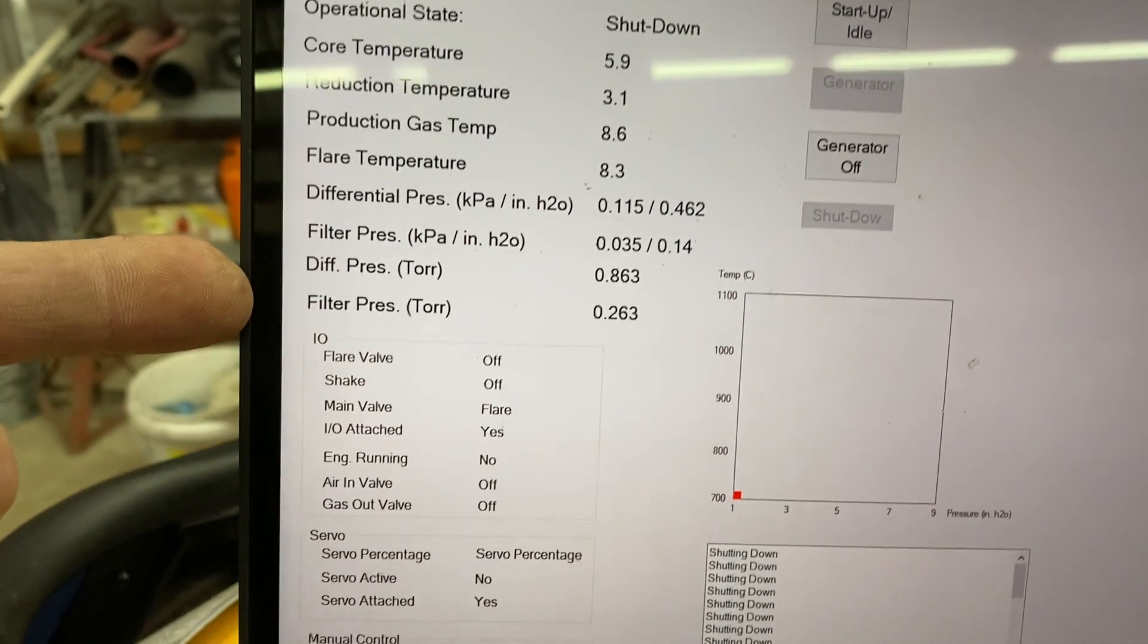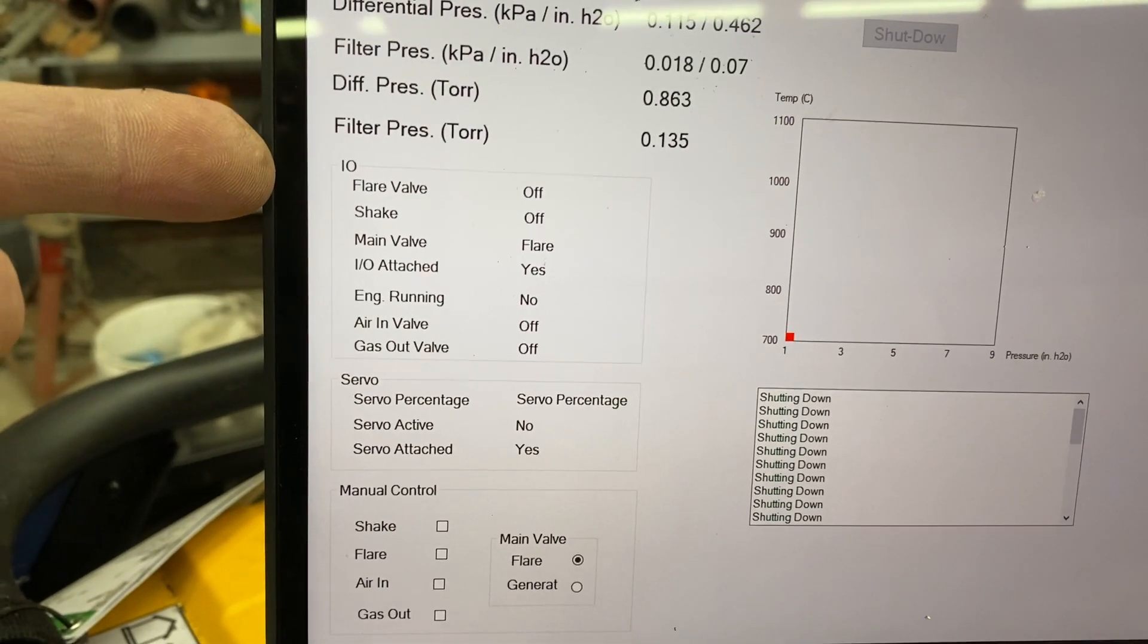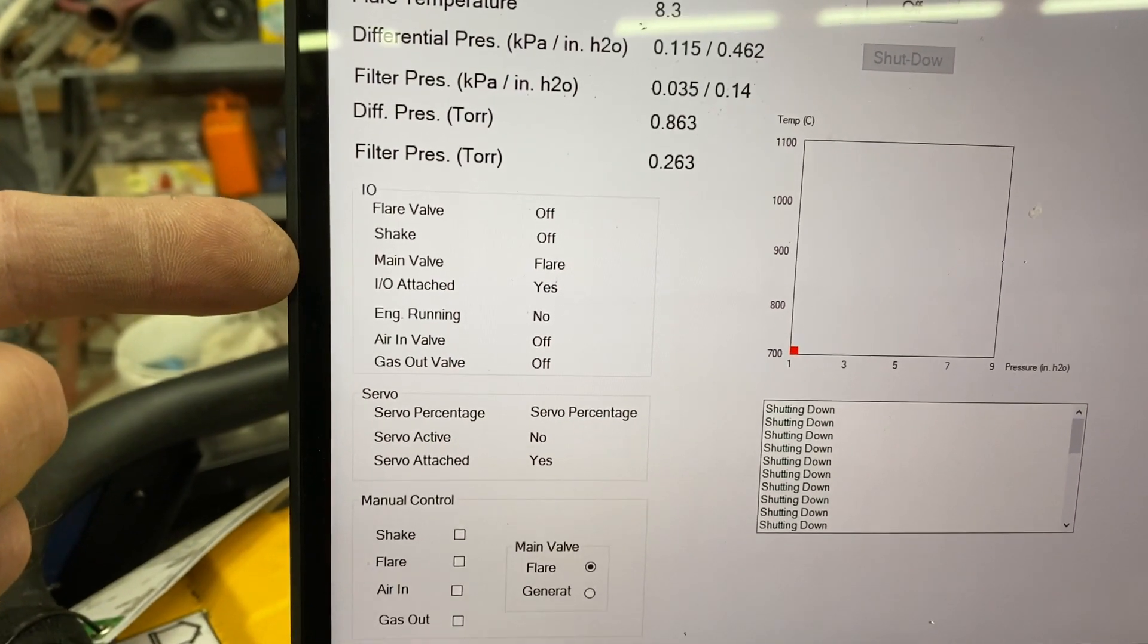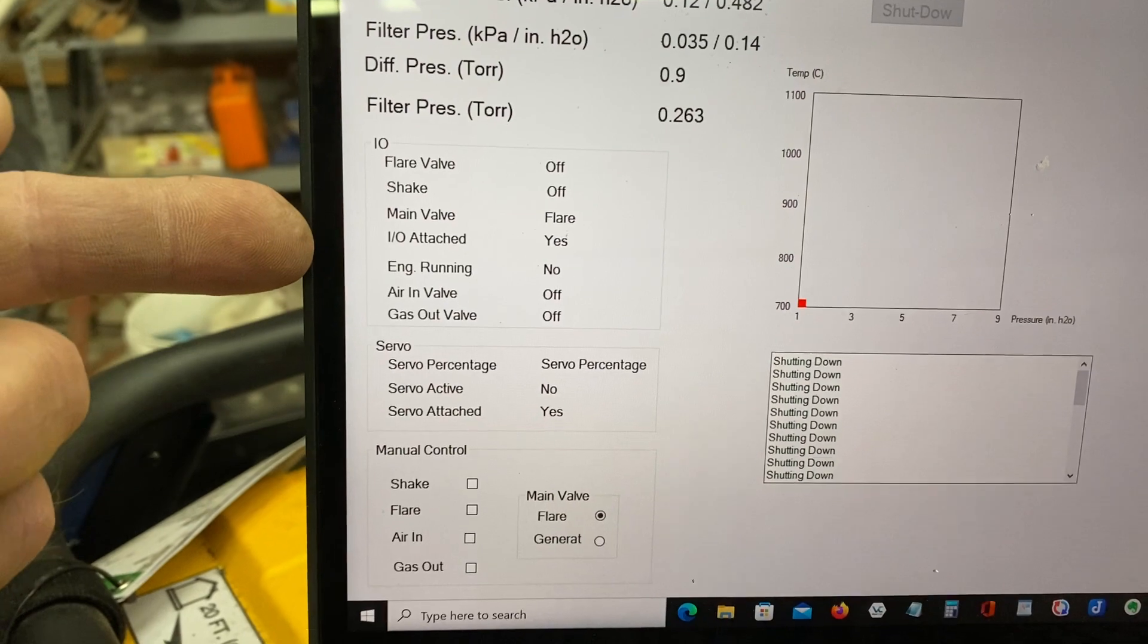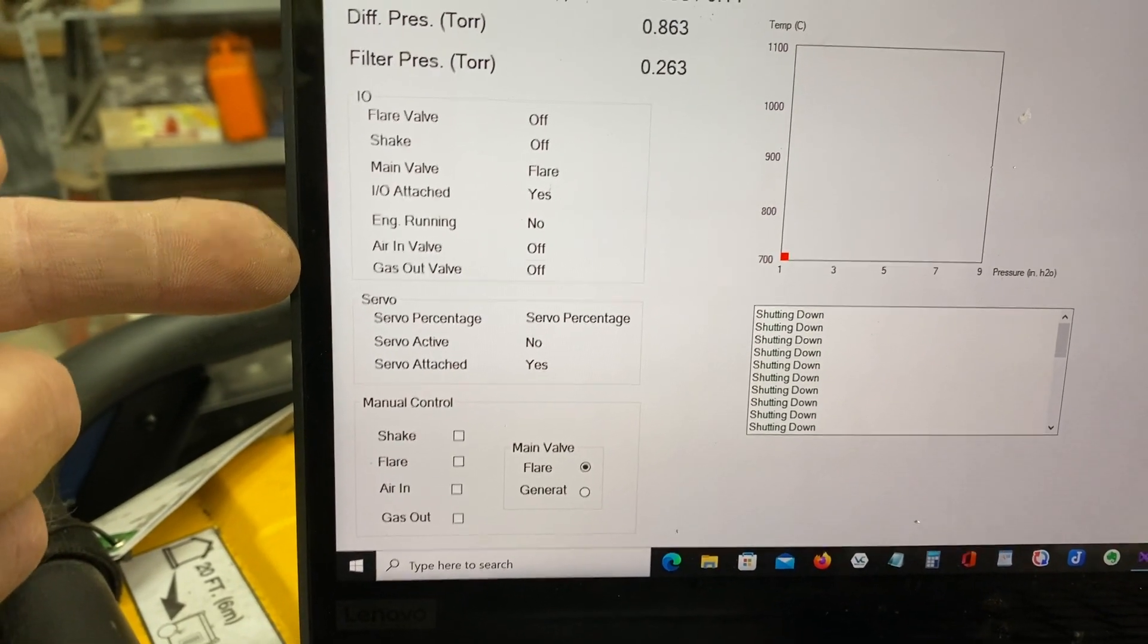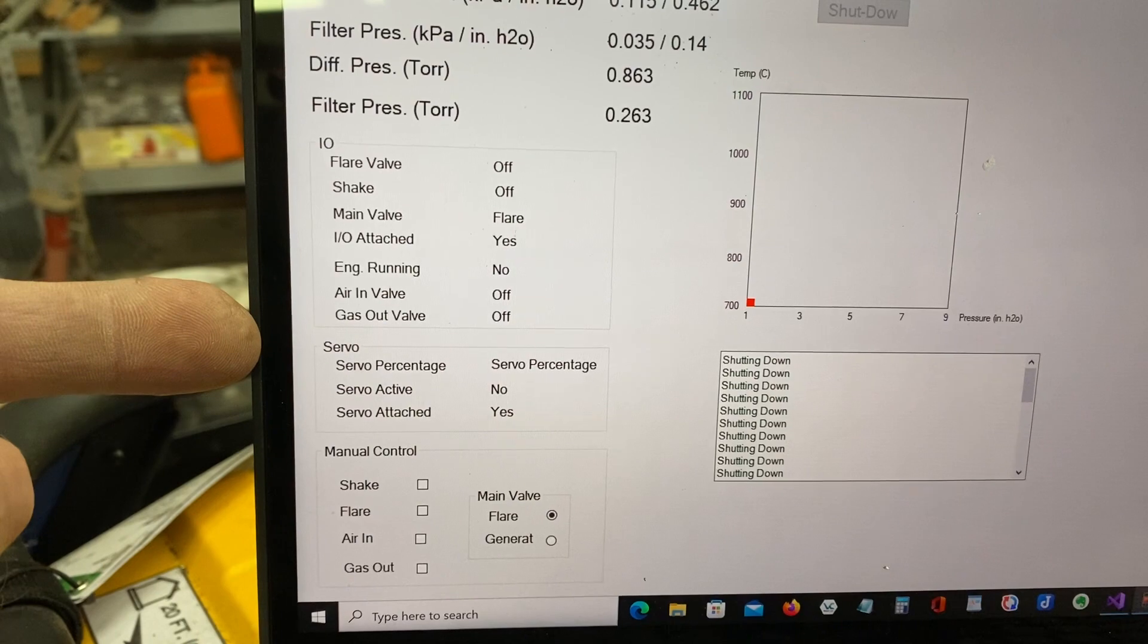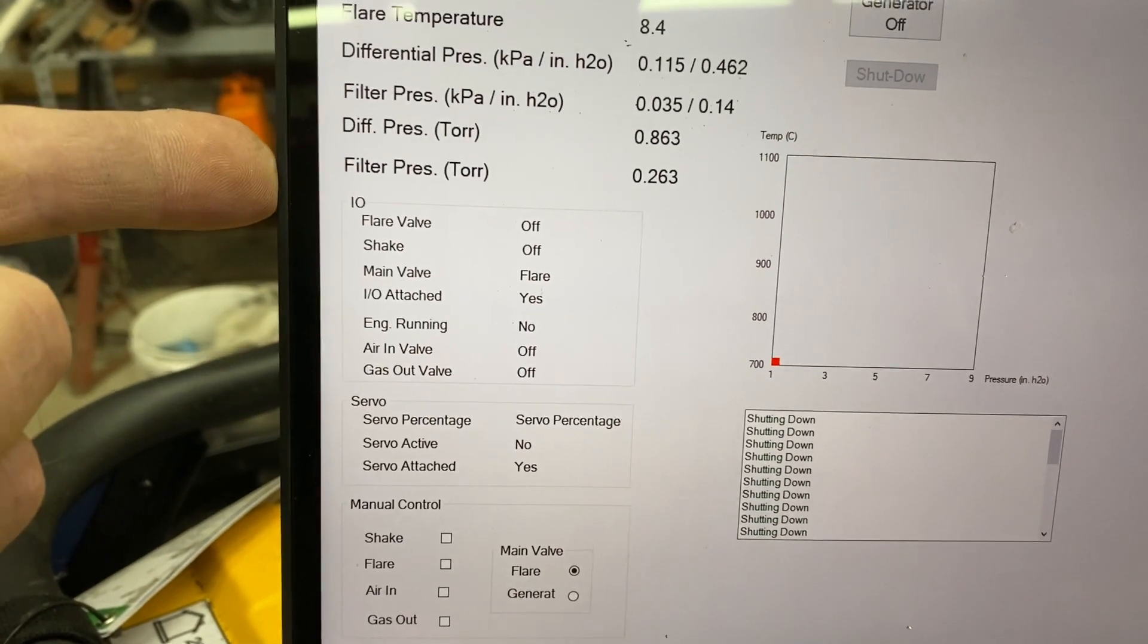So moving on down, the I-O state is listed here. So flare valve, when I trigger it on, it'll come on. And the shake, the main valve, which is not used anymore, it had an automatic valve that switched between flare and generator. That's been removed. I'll put it back later. I-O attached tells you that the computer's talking to the I-O. Engine running, pretty obvious. Air in valve, again, this is another valve that's not in service right now. Gas out valve, similarly, is not open. These are big solenoid valves that are not used right now. Everything's manual in terms of the valving, except for the shake and the flare.